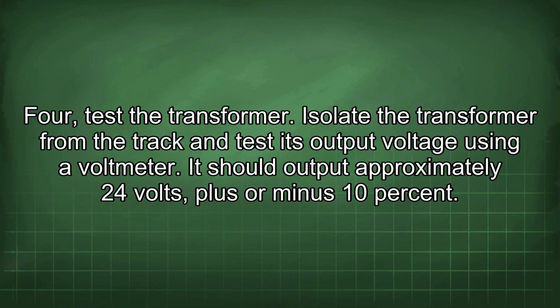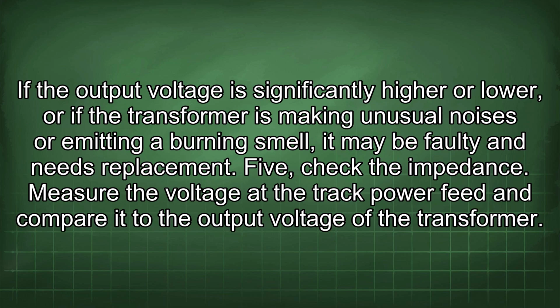4. Test the transformer. Isolate the transformer from the track and test its output voltage using a voltmeter. It should output approximately 24 volts plus or minus 10%. If the output voltage is significantly higher or lower, or if the transformer is making unusual noises or emitting a burning smell, it may be faulty and need replacement.